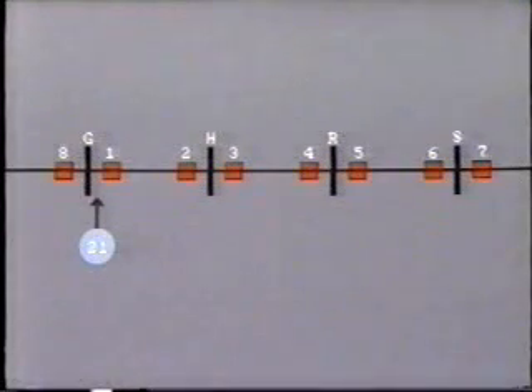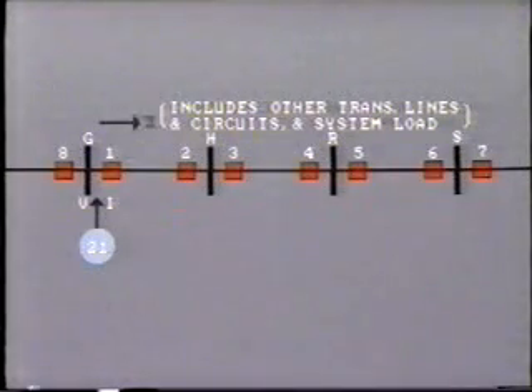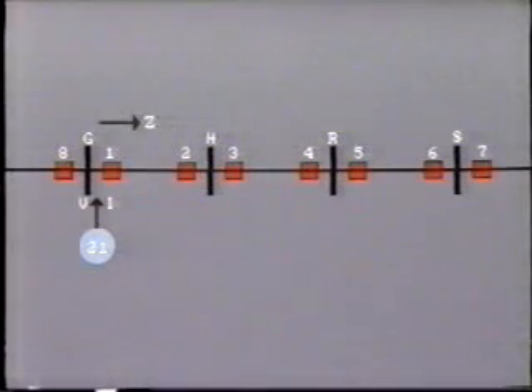Here, a distance relay is installed to trip the breaker number 1 and also to protect the transmission line between buses G and H. The distance relay measures voltage and current entering the line, and from this calculates the impedance downstream. This is the total impedance, including that of the other transmission lines and circuits and the system load. If a short circuit occurs, say halfway along line 1, then the total impedance measured by the relay will fall dramatically, and this will cause the relay to operate.